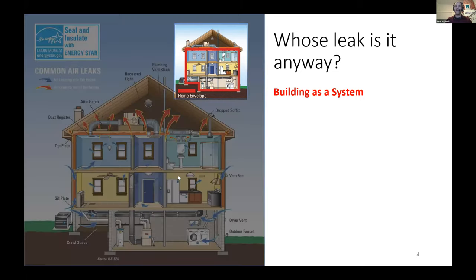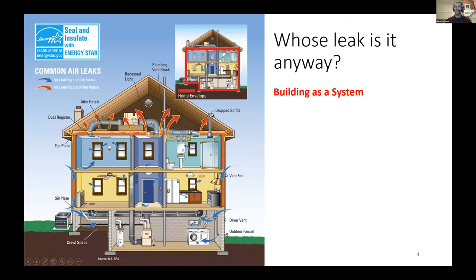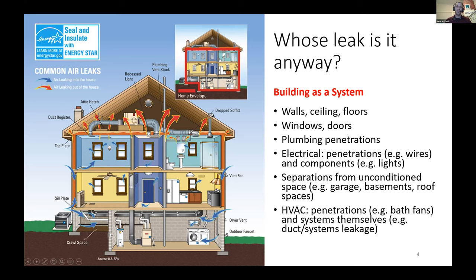So one thing that we want to talk about when we're doing a blower door test is that we're talking about the whole building as a system. The building envelope in this picture from the US government is this red box here in this graphic. So whose leak is the problem here? We're thinking about the building as a system. Well, there are many, many, many leaks that factor into the air leakage equation here. That includes not just the walls, the ceilings, the floors, the things you would buy Pro Clima membranes for, but lots of other things that we don't sell, like windows, doors, plumbing penetrations, electrical penetrations, HVAC, and then all of the transitions and joints between, say, conditioned spaces and unconditioned spaces. So it's actually quite a complex system.